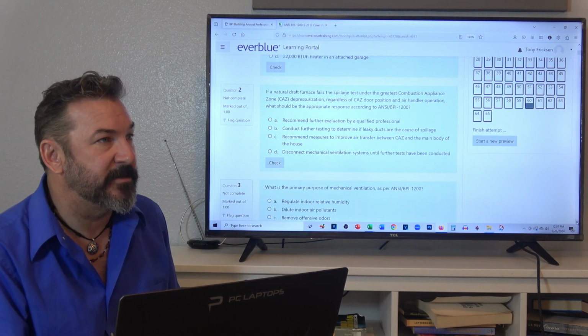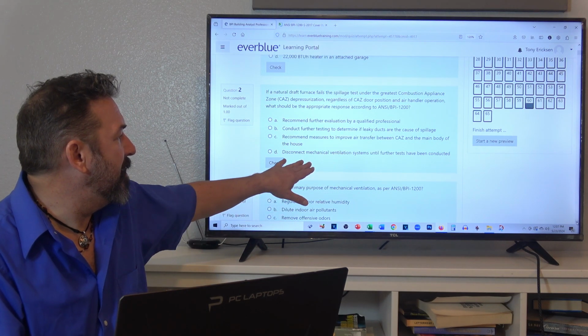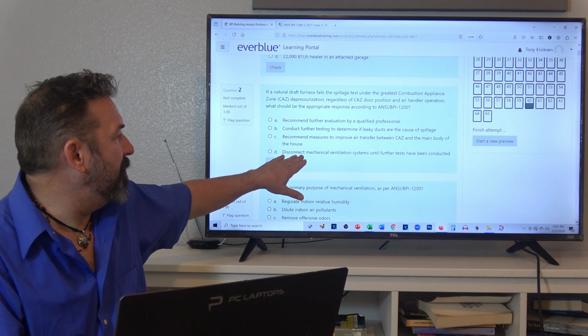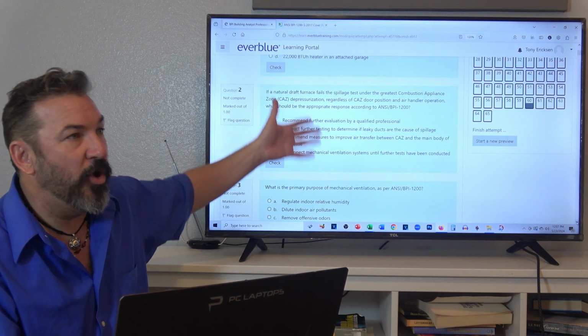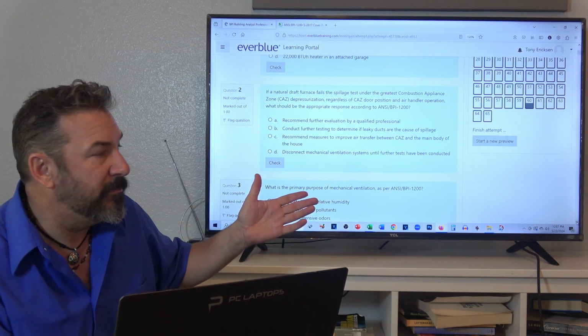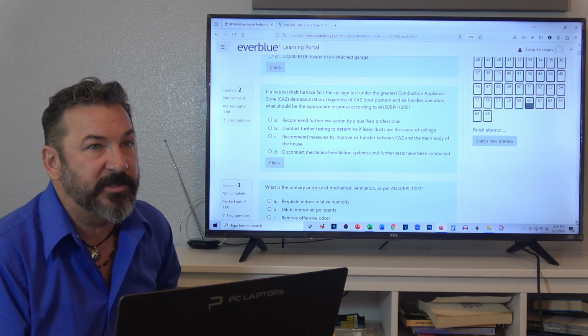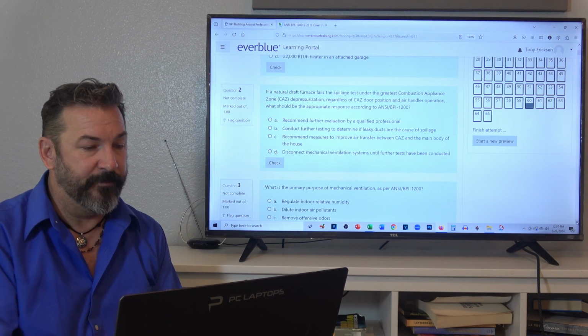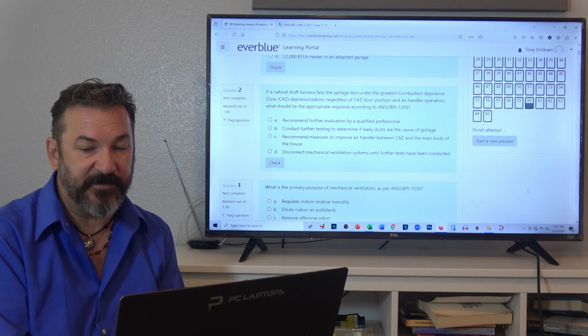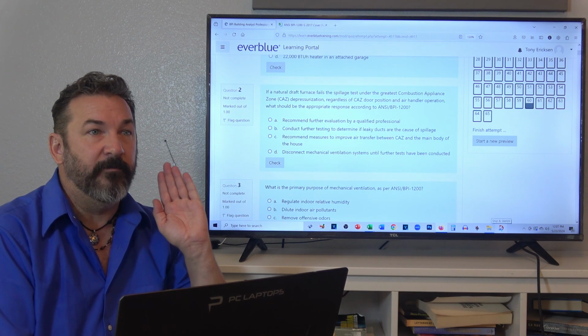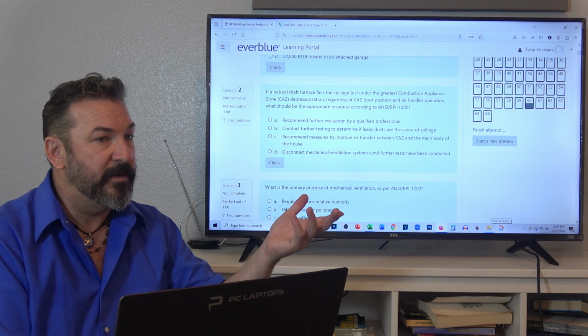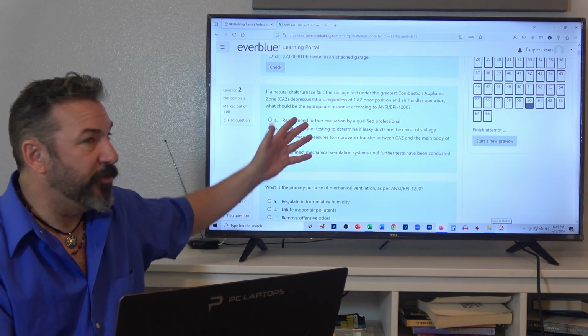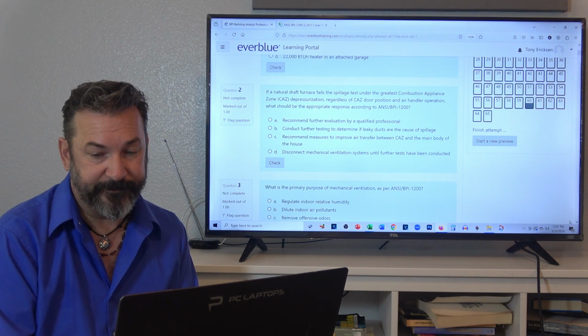Well, that doesn't make any sense. Okay? No recommendation says to disconnect it. So recommend further evaluation by a professional. Of those answers, that's the one, because the cause of the spillage has been determined to have to do with the exhaust.